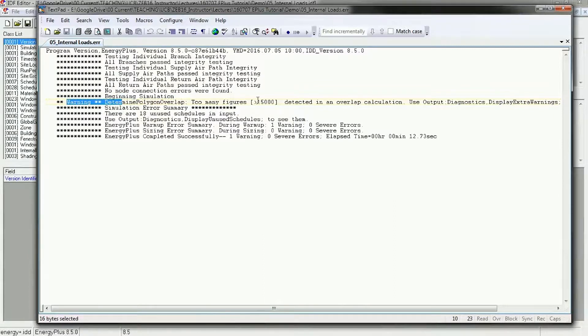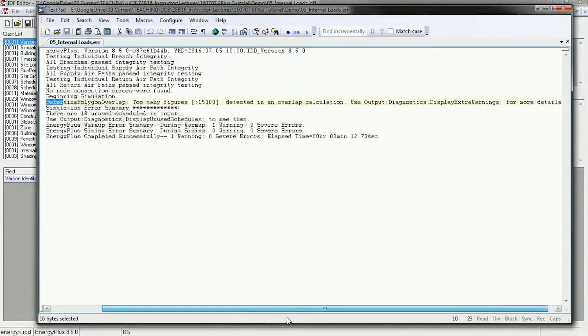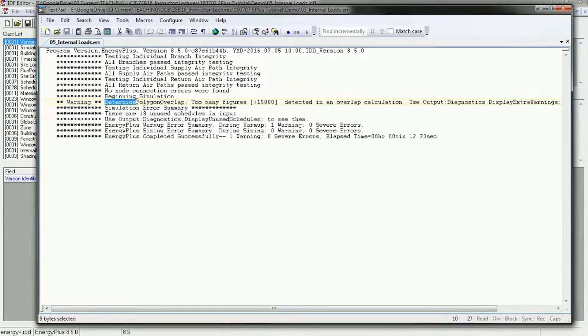Then it's beginning the simulation, and the warning we're getting is: determine polygon overlap — too many figures greater than 15,000 detected in overlap calculation — use output diagnostics display extra warnings for more details. If you want to figure out more about this error, you could Google it, go to the Unmet Hours website, or look in the Input Output Reference. This is a common thing to get when you have a lot of context shade; in this case we've got a lot of louvers on our model that are overlapping, and the simulation should run okay even with this warning.